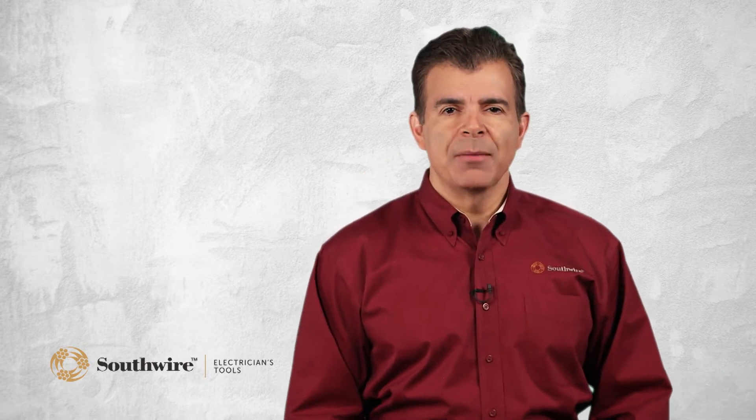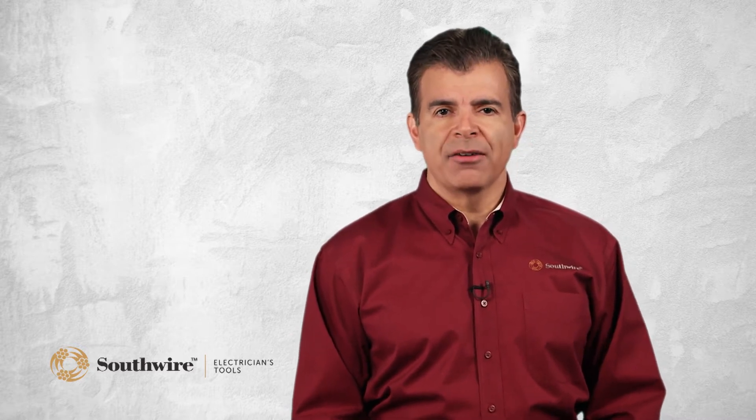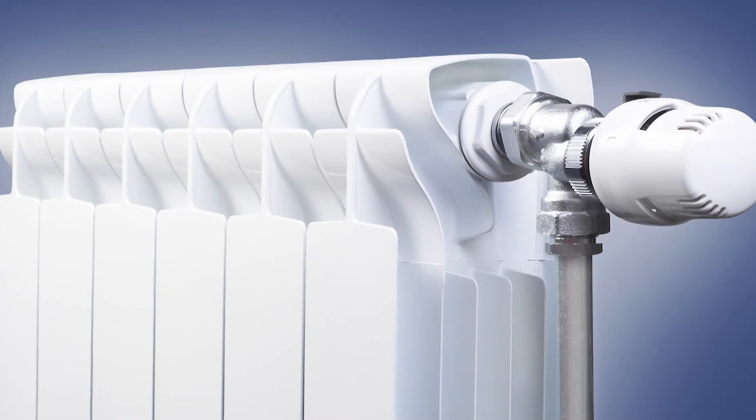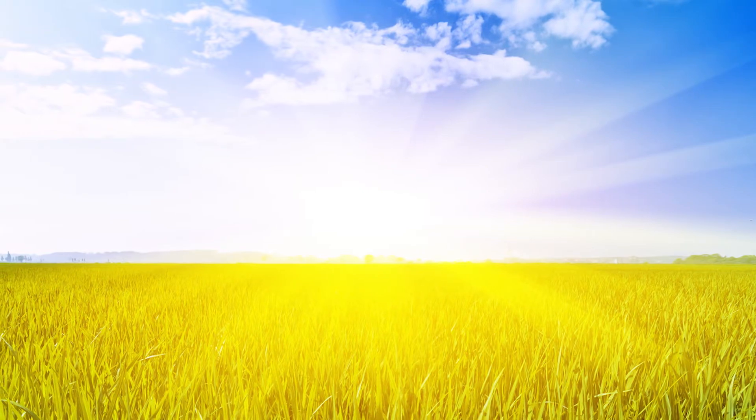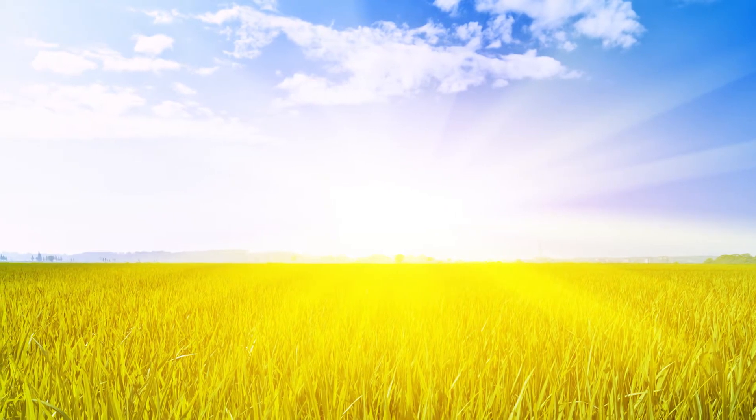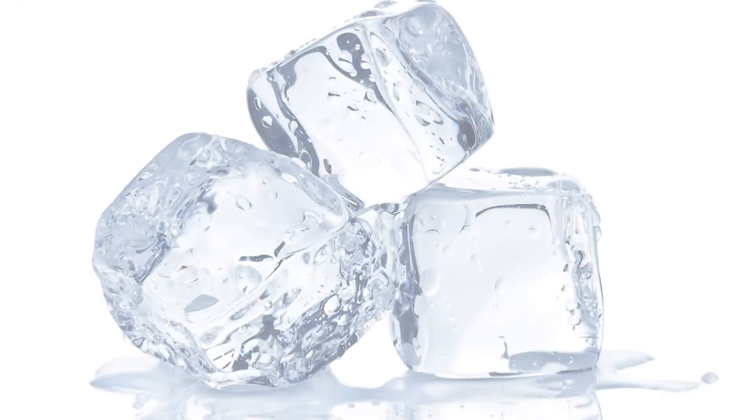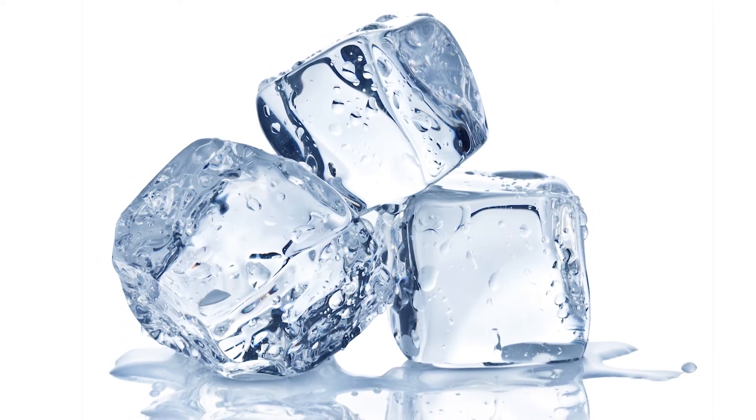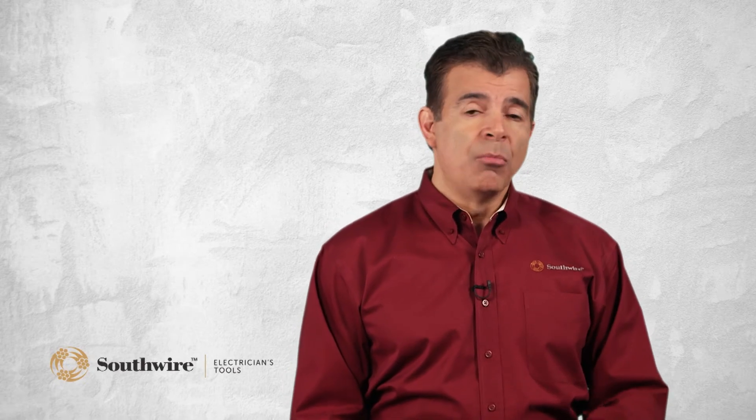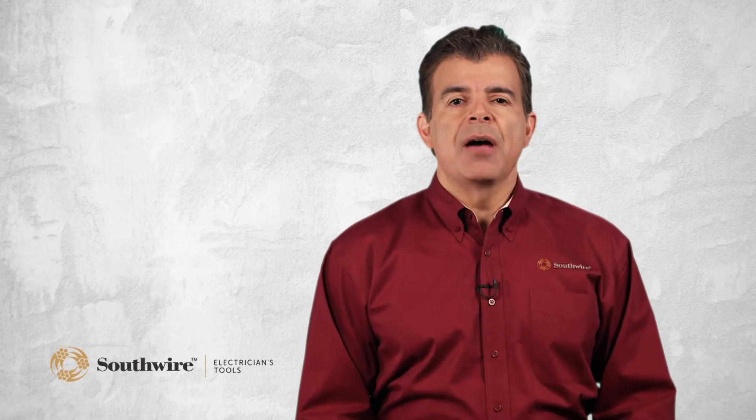IR thermometers measure temperature by detecting infrared energy. We experience infrared energy every day. When we stand close to a radiator or fire, or go outdoors on a sunny day, the heat we feel is infrared energy. All objects emit infrared energy. Even a very cold object, such as an ice cube, emits infrared energy. As an object gets hotter, more infrared energy is emitted. This phenomenon is very predictable, which allows calibrated temperature readings to be made by measuring the amount of infrared energy an object emits.